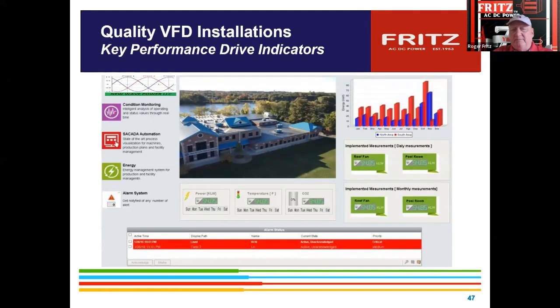This happened to be on a facility up in the Lowell area where you can see here, this was the loading factor of everything prior. And by the time we put in the BMS and drive controls, we ended up seeing about a 45% reduction in their total power bill.